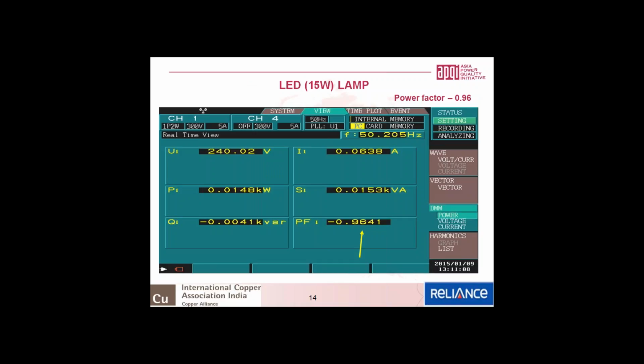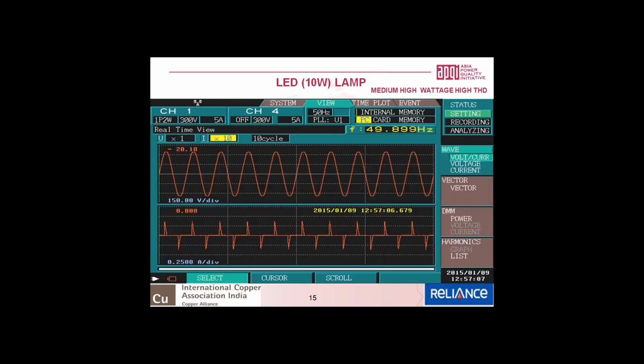But in the market, we also have some LEDs whose current waveform we have picked up, which you can see at the bottom. This is a 10-watt lamp of some other manufacturer. You can see the current waveform here. It doesn't even remotely look sinusoidal. It looks like a simple series of triangular pulses. Therefore, you can anticipate that the total harmonic distortion of the current could be very, very high.